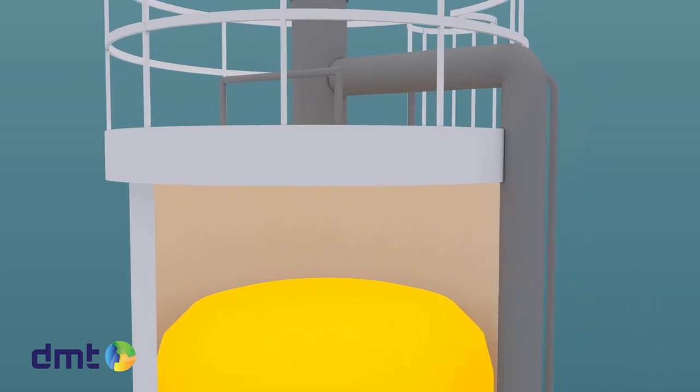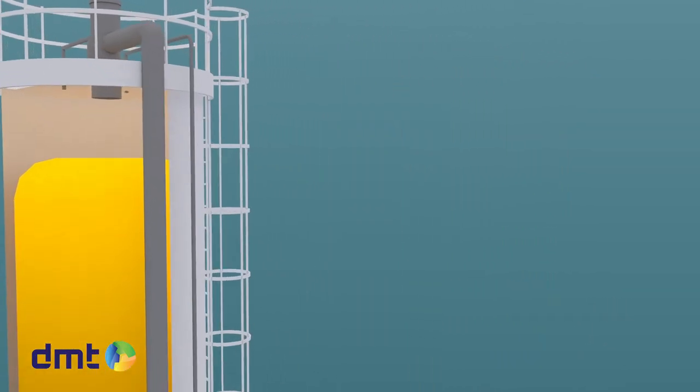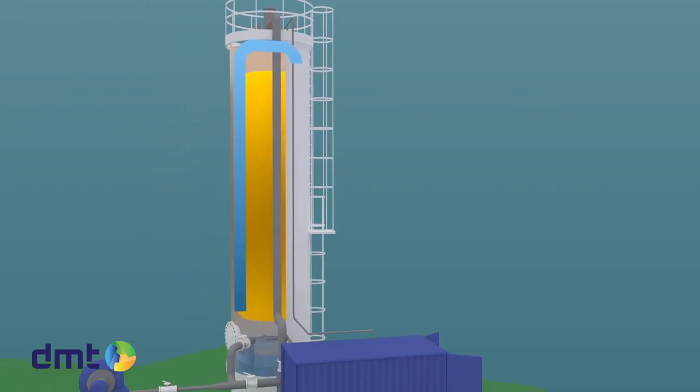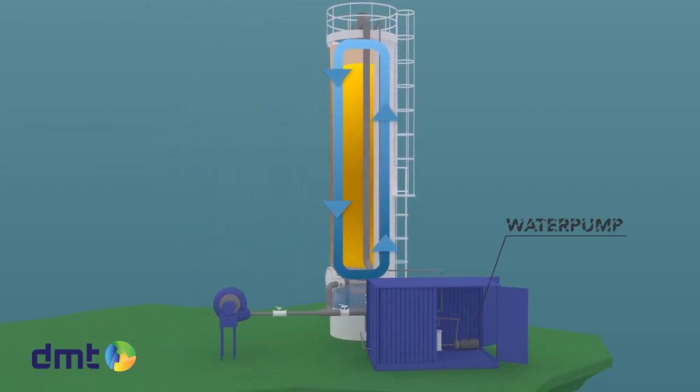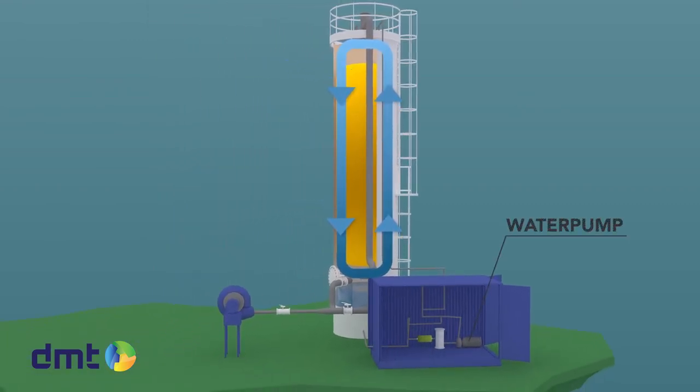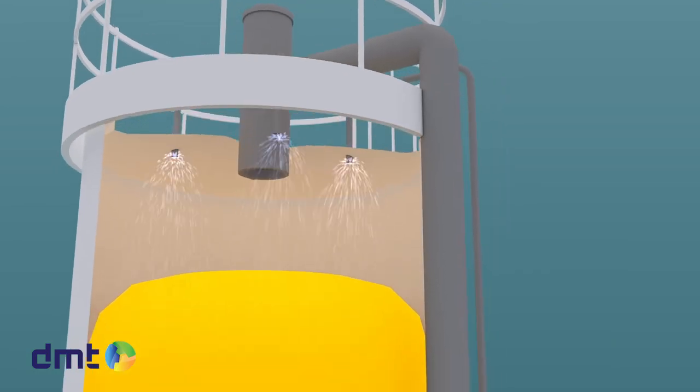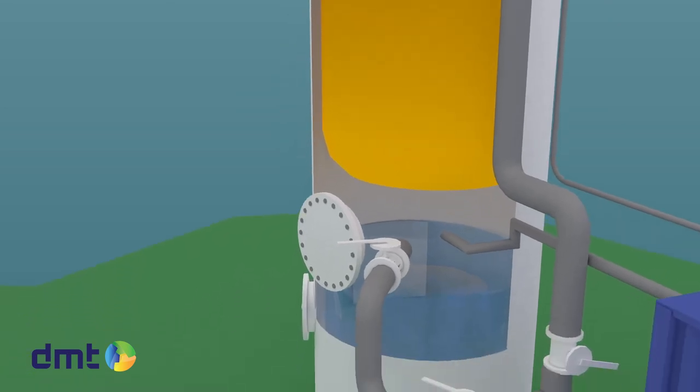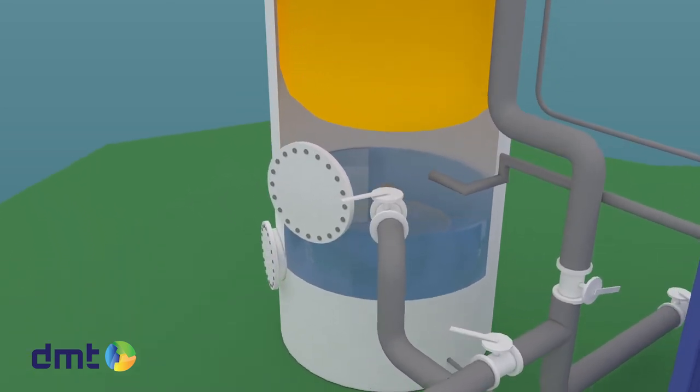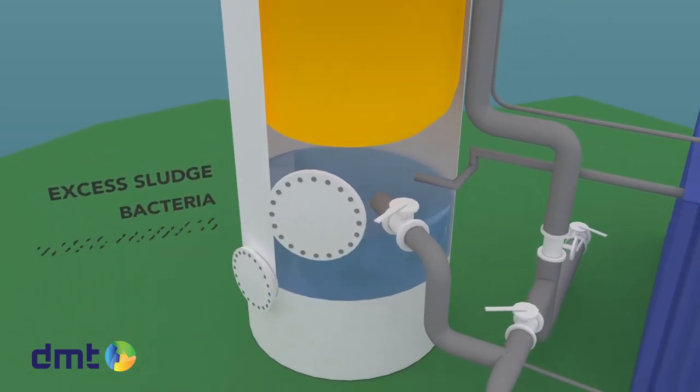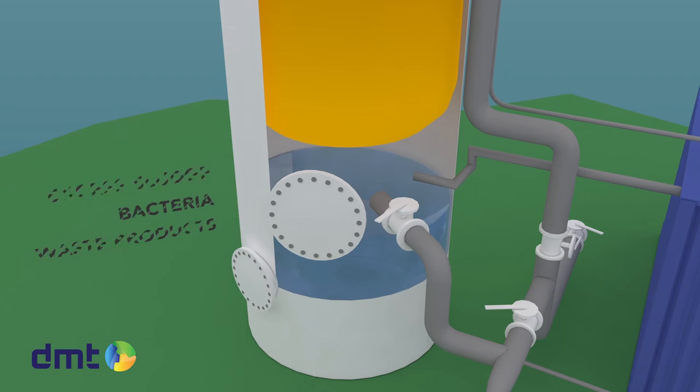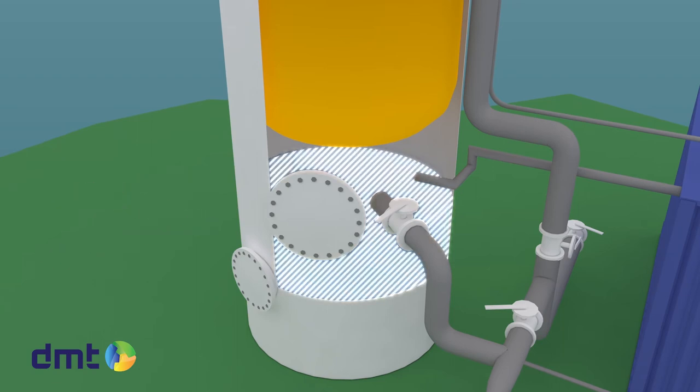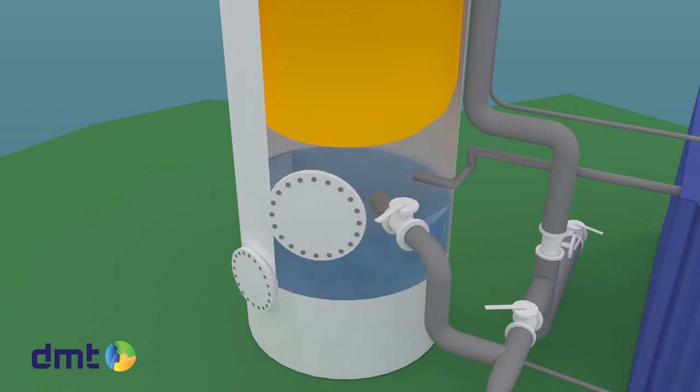Since bacteria are living organisms, they require water to sustain them. Therefore, water is circulated through the packing material by a circulation pump. The water is sprayed on top and trickles down through the packing. The water also functions as a sewage system to discharge excess sludge or bacteria and waste products. The water is collected in the buffer at the bottom of the system where it can be recirculated again.